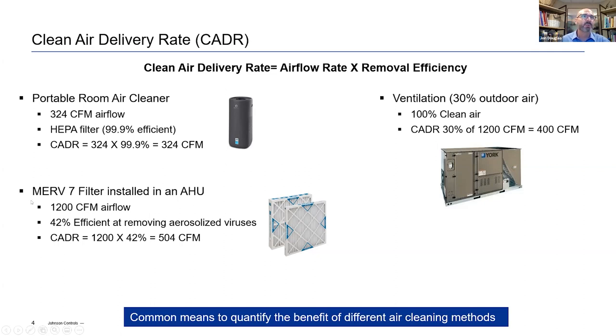And then there's just another example where you can take a MERV 7 filter, roughly 42% efficient, not super efficient, but because it's moving a ton of air, it still actually does some air cleaning. So you get some airflow rate and cleaning from that unit. You get 504 CFM of clean air. The good thing about this is a means of quantifying the air cleaning rate of different types of IAQ mitigation measures. So we have one common measure to put them all together.